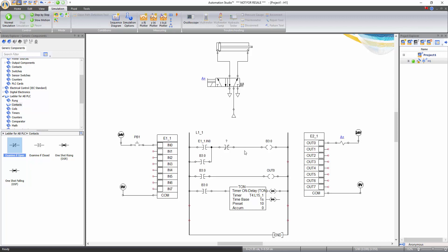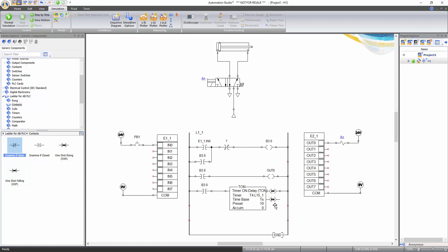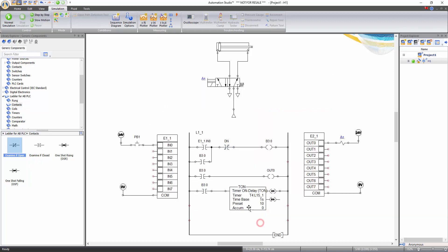Once the on delay timer is in place and connected, add the timer done DN contact to de-energize B3:0 once the preset time is reached. Drag and drop an examine if open contact from the contacts category of the ladder for AB PLC library directly on the first line between E1_1.IN0 and B3:0. When dragging a component from the library, if you drop it directly on the line, it will automatically insert that component in the circuit. Note: if you drop the component on the workspace first, the ports remain red, indicating the component is not inserted correctly — delete it and try again. Link the examine if open to the timer done bit DN. Double click on it to open the component properties window, search for DN in the filter, and double click to establish the link. By default the timer has a preset time of 10 seconds; change it to 5 seconds by double clicking the timer on delay, going to the data tab, clicking the star to display all fields, finding the preset time field, and changing the value to 5 seconds. Then exit the window.